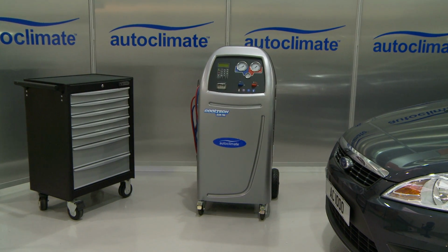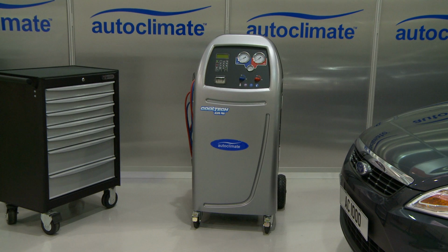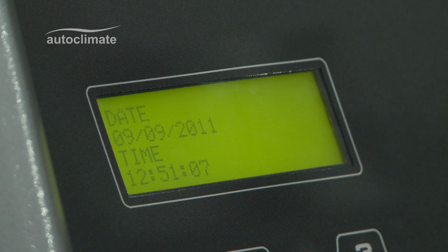This AC690 Pro video explains the manual charge process. Please note that if dye or oil is to be injected, a manual vacuum must have been carried out before activating a manual charge. Switch the machine on, and after initializing, date and time are displayed.